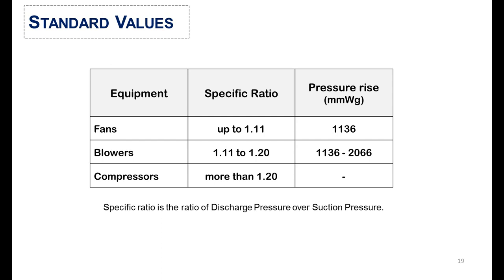Finally, there are standard values comparing fans, blowers, and compressors. The specific ratio — which is the ratio of discharge pressure over suction pressure — should be up to 1.11 for fans, between 1.11 and 1.20 for blowers, and greater than 1.20 for compressors.